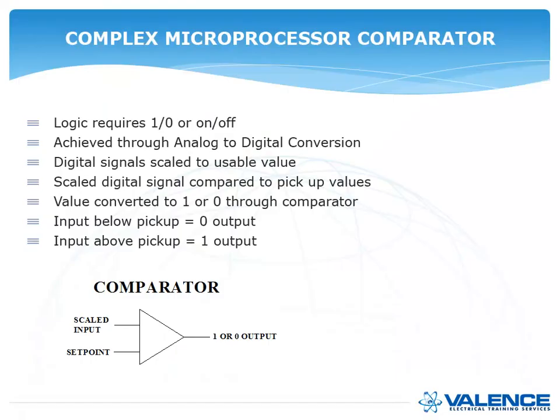When you're looking at the logic, the first thing that digital relays do is they're always comparing. They're comparing their analog signals to a setting. A comparator is often described as a triangle with an input on the top and a set point on the bottom. So if the line on the top is greater than whatever the line on the bottom is, then it's going to give you a 1 or a 0 output — so on or off.